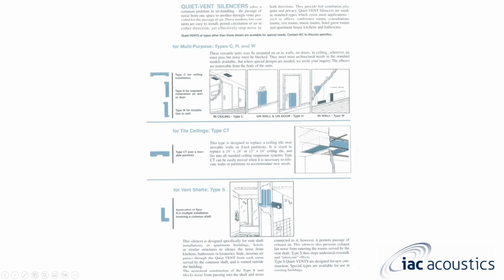These are excellent. A good example is in hotel rooms, between rooms, to quell noise from one room to the next. That way you don't hear your neighbor, you apply these type S vent shafts, and air goes straight up between the walls. The military likes to use these between rooms. They also like to use the CT between rooms, because some of the rooms have removable partition walls. That way, say a movie is being played in one room and a pilot is going over his assessment in the other, the two do not hear each other and cancel each other out.